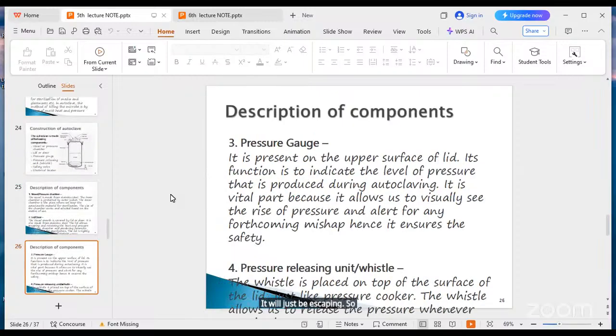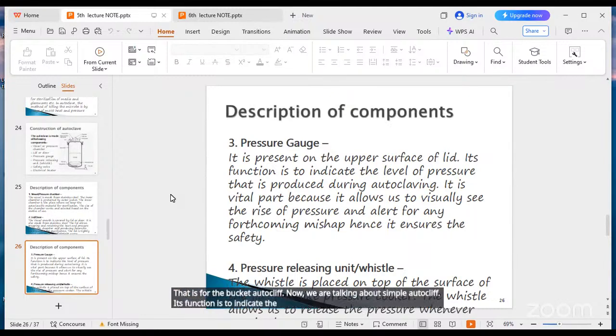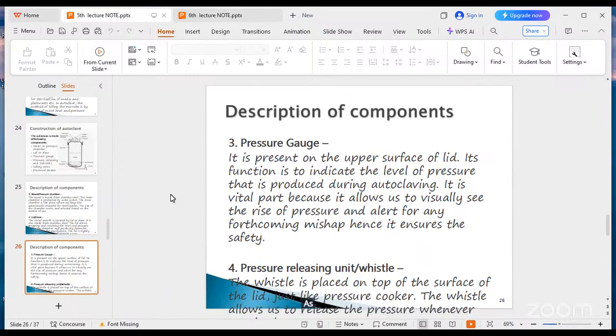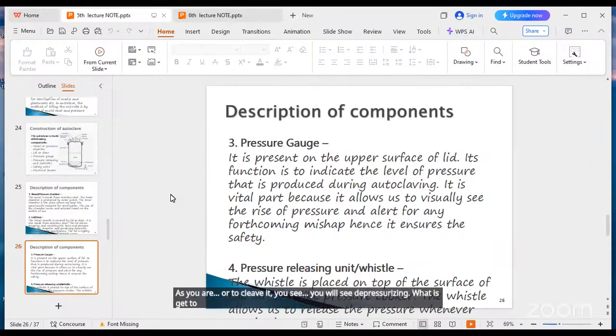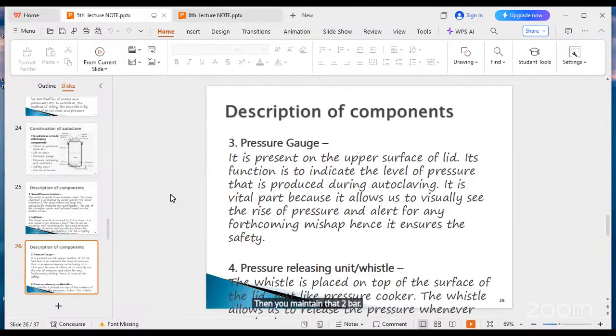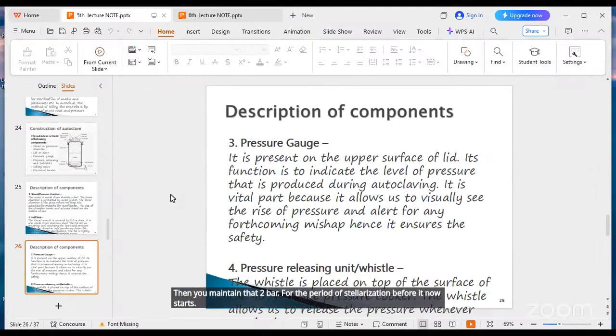Now the pressure gauge. What is the function of the pressure gauge in an autoclave? It is present on the upper surface of the lid. That is for the bucket autoclave. Now we are talking about the simple autoclave. Its function is to indicate the level of pressure that is produced during autoclaving. As you are autoclaving, you will see the pressure rising. When it gets to a certain pressure, let's say 2 bar, it is maintained at that 2 bar for the period of sterilization before it starts falling gradually.